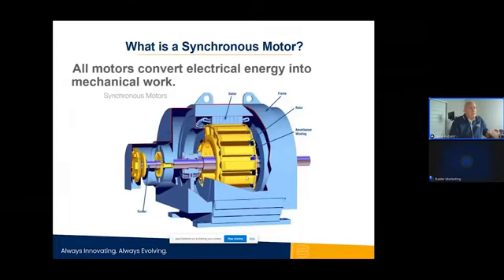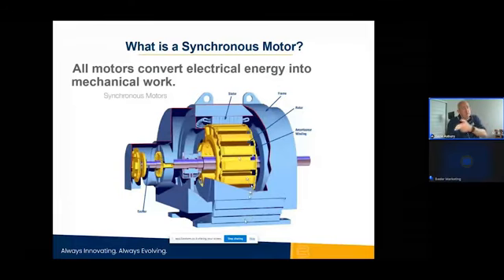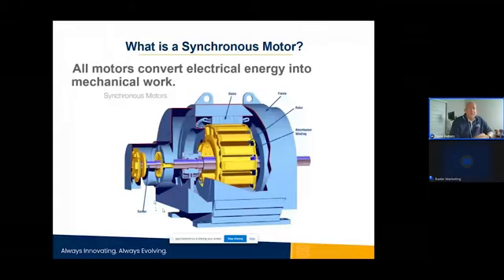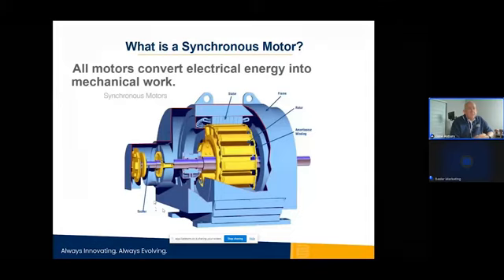And since typically the synchronous motor isn't self-starting, you need that squirrel cage winding to get that action to take place. Also, what makes a synchronous motor different than the induction motor is a separate source of excitation that is provided to the field winding to interact with the RMF of the stator winding. So as it approaches synchronous speed, you would need some outside source to excite the rotor winding or the rotor field to pull that rotor into step with the stator field. And that's done by using different relays or control elements that we will talk about in the near future.